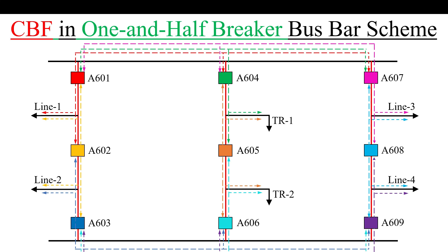I take a one-and-a-half breaker busbar scheme. In this scheme we have two buses, and in between three breakers. Between these three breakers we can connect two circuits, for example transmission lines or transformers. For simplicity, I make each breaker a different color so it can be easily differentiated.